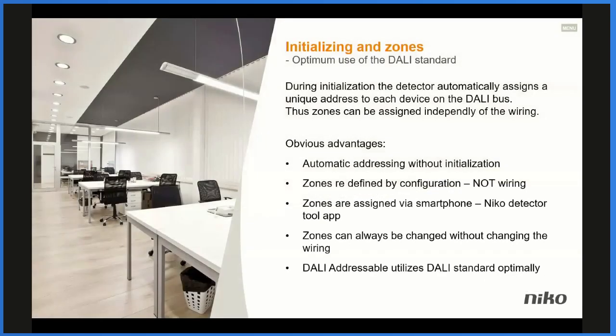For the installation, you have an optimal use of the DALI standard because we are following this standard, and it will be done automatically. You don't need to do anything. The detector will take care of that, so you don't need to think about it. You can redefine zones by configuration, not by wiring or rewiring. You just move one detector from one zone to another. The commissioning is done by the smartphone and the Niko detector tool app, along with the dongle. I'll show it a little bit later.